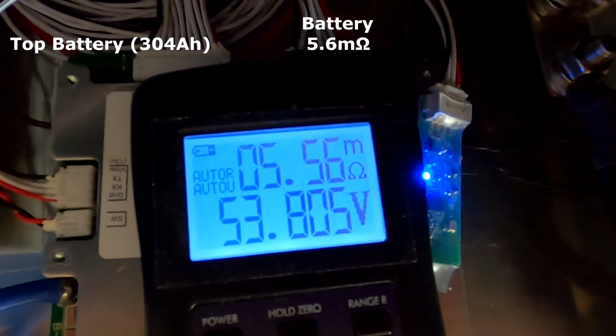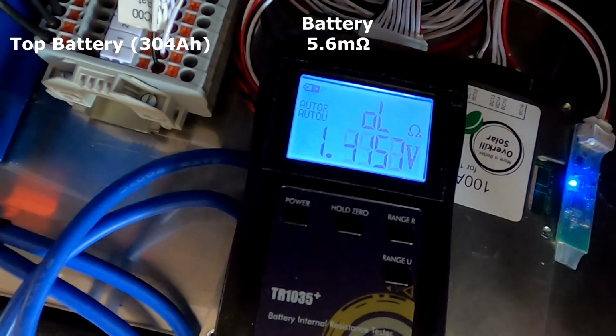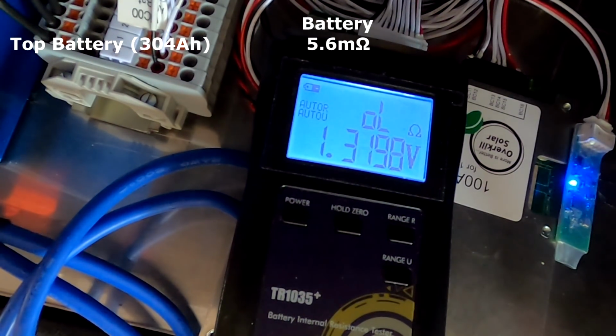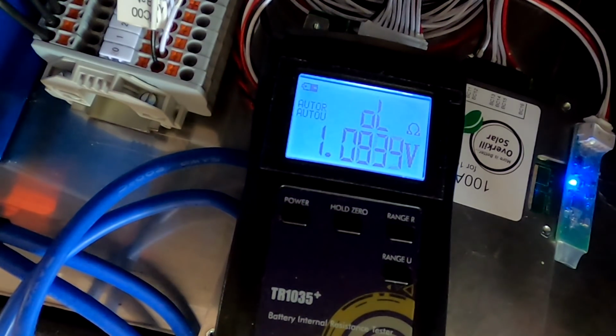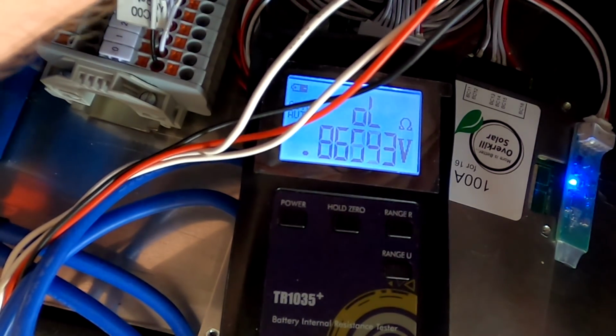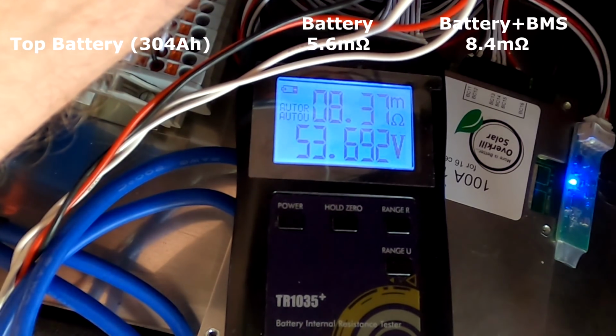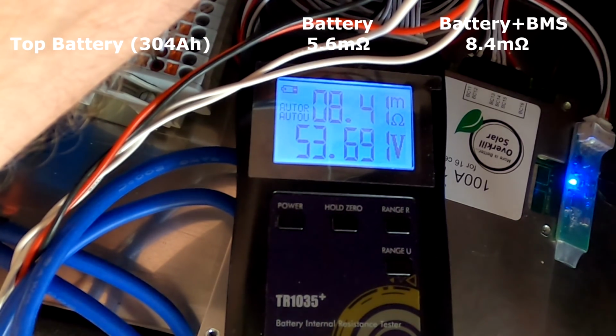5.56 milliohms - so this was the pure battery from positive to negative terminal across all the terminal and bus bar connections. I want to do a second measurement here on the output or input of the circuit breaker, so we measure including all the cabling and BMS. There we go, that's the second measurement: 8.4 milliohms.